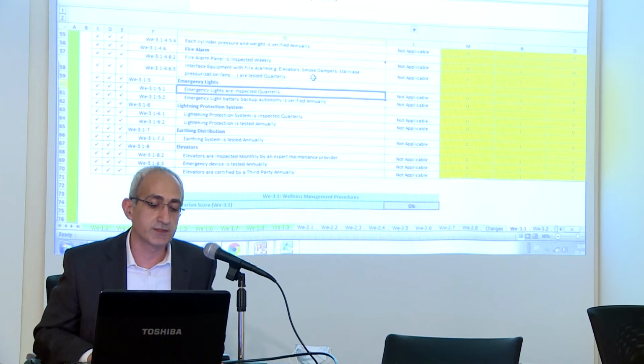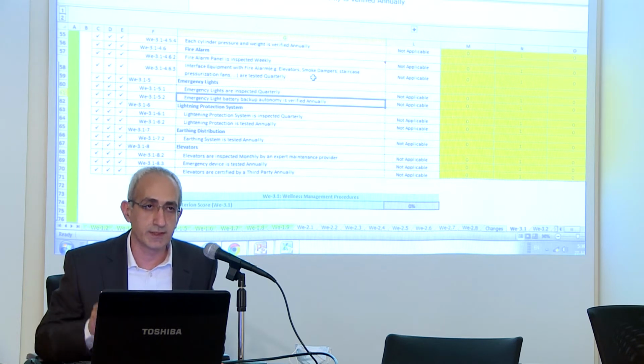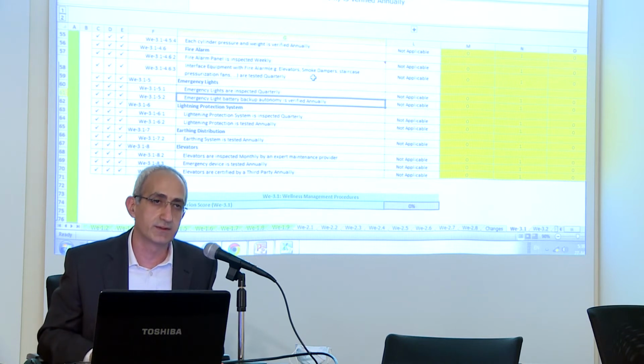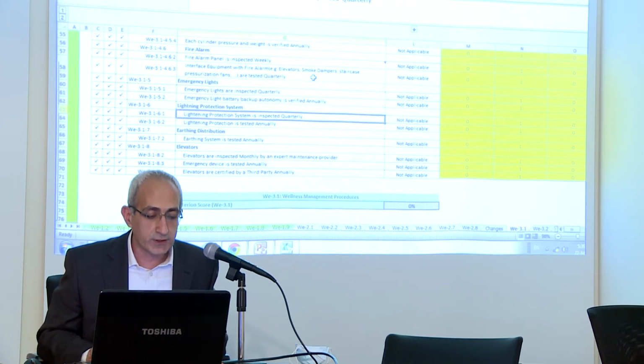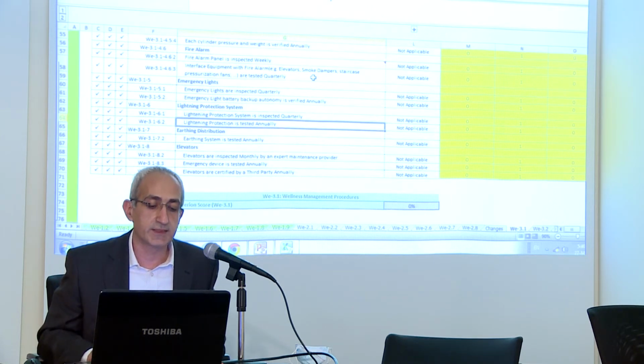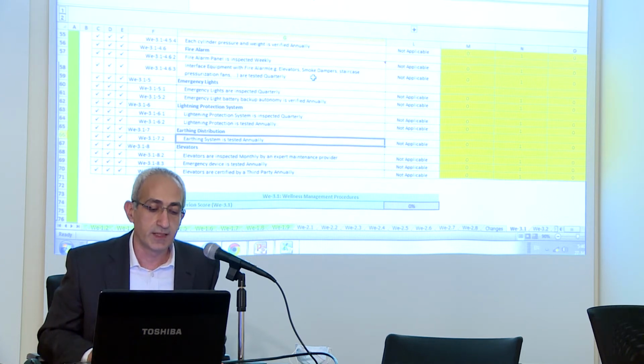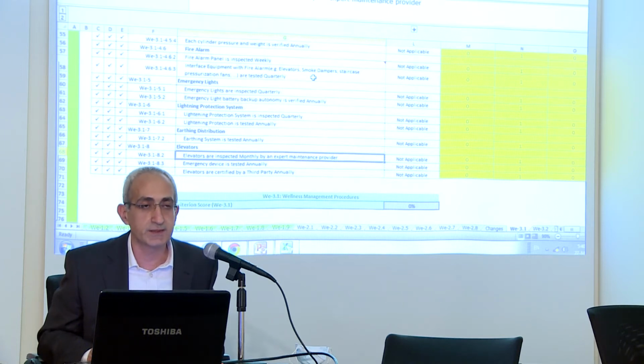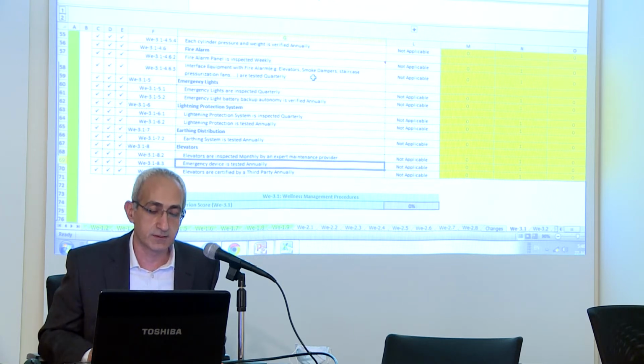Emergency lights are inspected quarterly, visually, and for backup autonomy. If you've requested 2 hours or 3 hours, depending on the standard you're applying, the autonomy should be verified annually. So we switch off power and we time the fixtures. Lightning protection system is inspected quarterly for loose connections, visually, and then tested annually. Earthing system, tested annually. Elevators are inspected monthly by an expert maintenance provider. This is a specialized maintenance provider. The emergency device, the parachute of the elevator, is tested annually and certified by a third party annually. Not many buildings do that, if any.